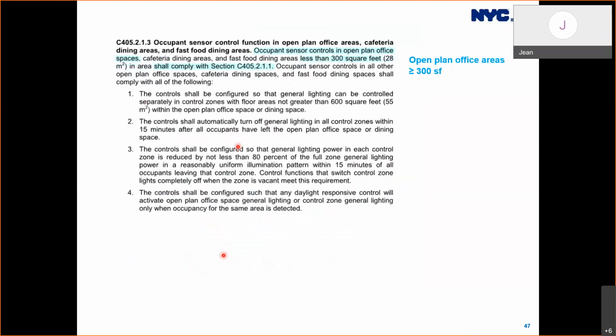And this is the other section that the previous section pointed to. According to this section, open plan office areas of 300 square feet or greater must comply with all of the following. If you look at it, it's talking about maximum control zone size, automatic turn-off after 15 minutes, and a minimum of 80% of the full lighting must be turned off within 15 minutes of non-occupancy. And this is about daylight responsive control. So it looks like there is nothing about manual control for these larger open plan office areas.